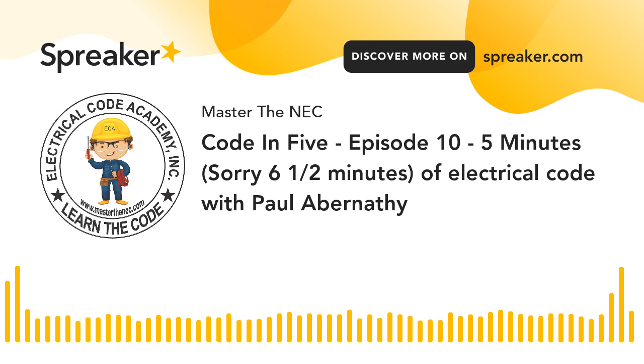Now, what about that 90-degree rated insulation? It goes on to say conductors with temperature ratings higher than specified for terminations shall be permitted to be used for ampacity adjustments, corrections, or both. Again, we said it was a 60-degree terminal, and we're using 90-degree rated insulation. So, can I use 90-degree rated insulation and maybe have an adjustment and correction? Absolutely. The code is telling me I can do that.